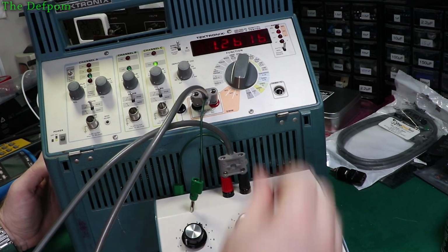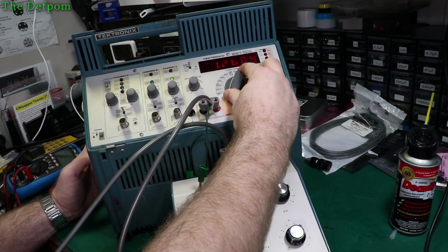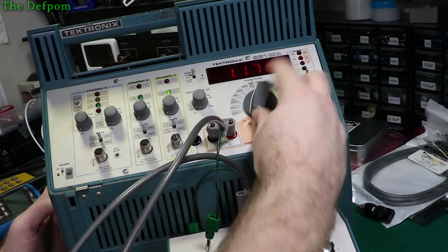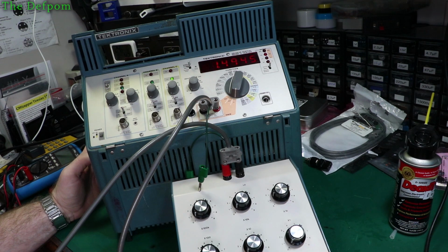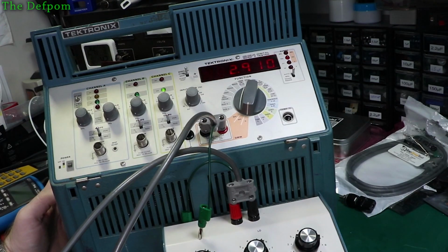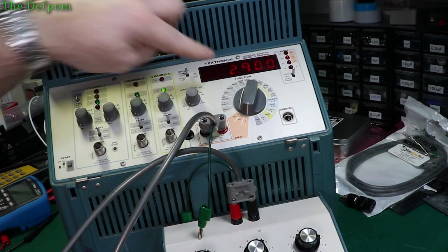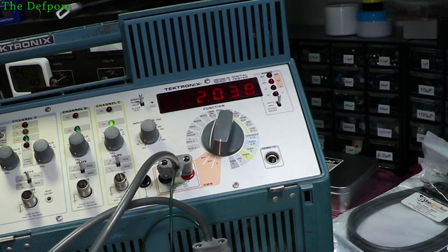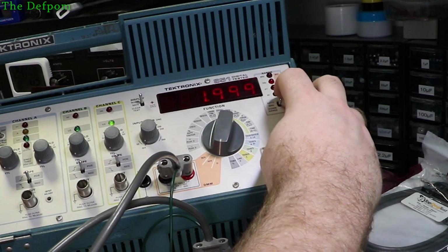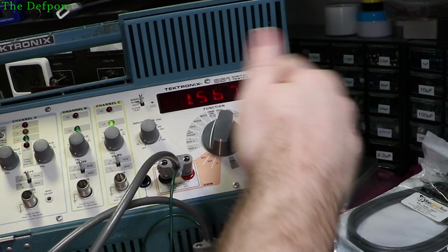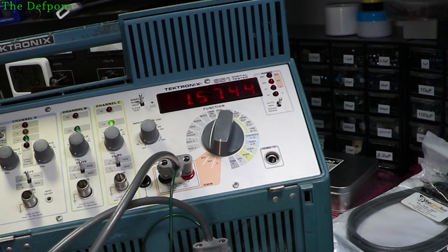I'll do 1.5K. 1.26. Give the knob a little wiggle. The knob's behaving a lot better. That's not playing up now. That's good. I think I've fixed that problem at least. But the reading's completely wrong. The 1.9K, I get 1.5. If we go to 2.9K, I'm getting 2.9 in that range. So that's correct. So 2K on that range there. That's right. If I downrange, I get 1.56. Hasn't improved it. Well, not much. It has changed, but hasn't improved it much.